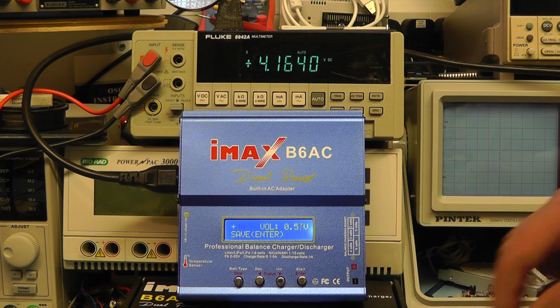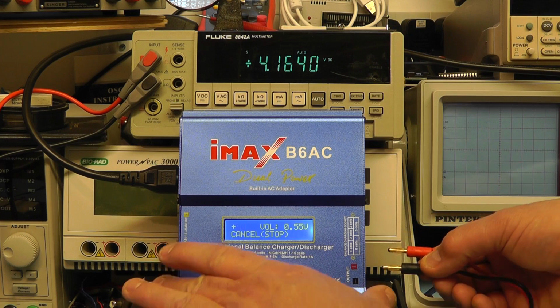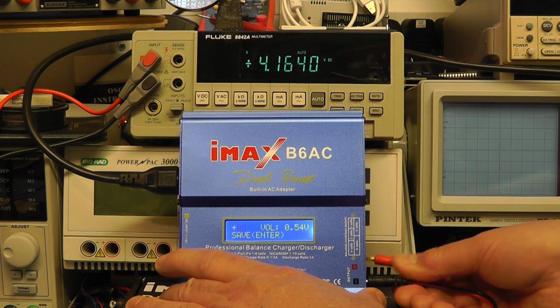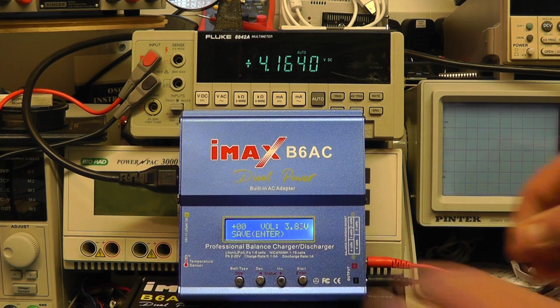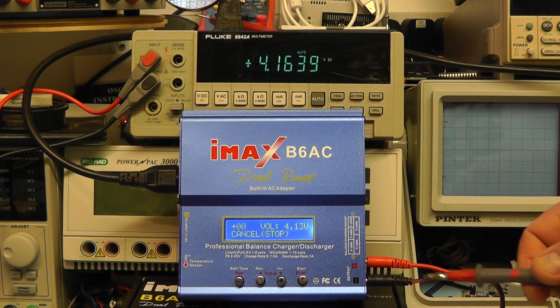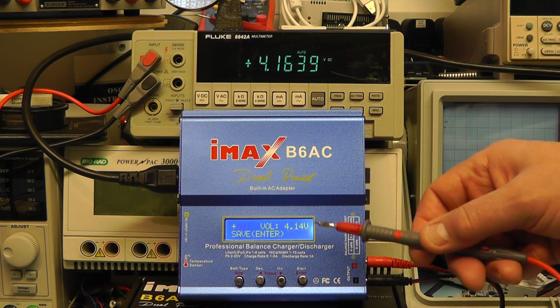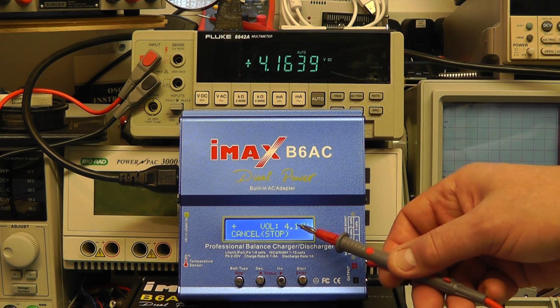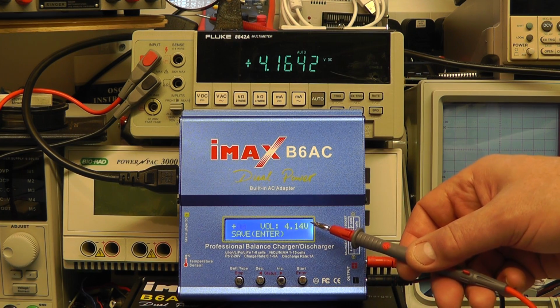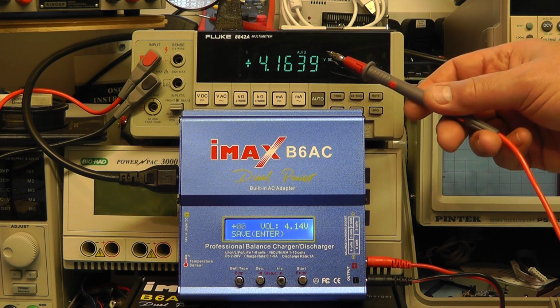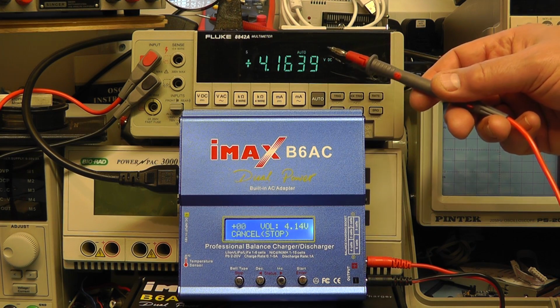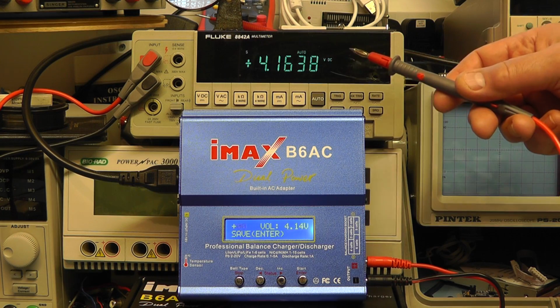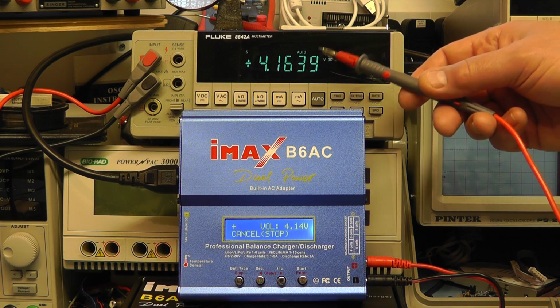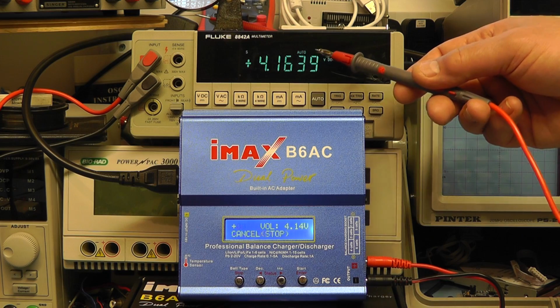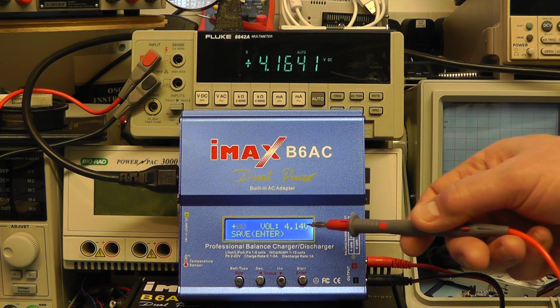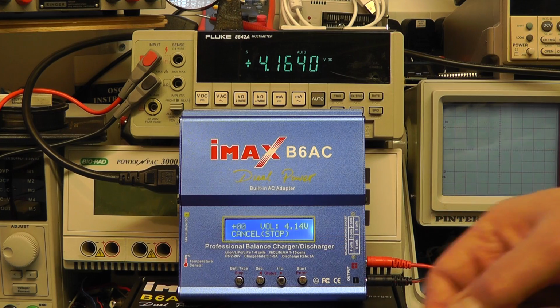What I'm now going to do is plug in the battery that I just checked. And you can see straight away that the battery is actually reading 4.14 volts on the unit, whereas when we look at the test meter it's showing a reading of 4.163, or 4.16 volts, as you see there. So we need to adjust the unit so the voltage matches the true voltage of the battery.